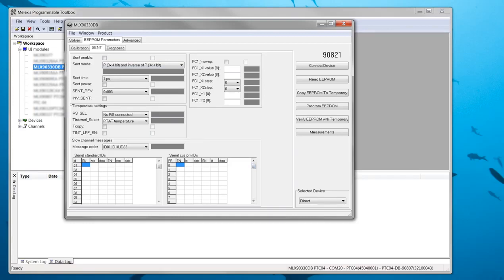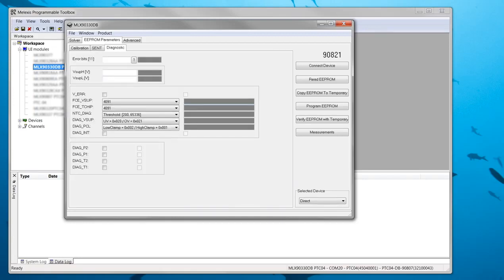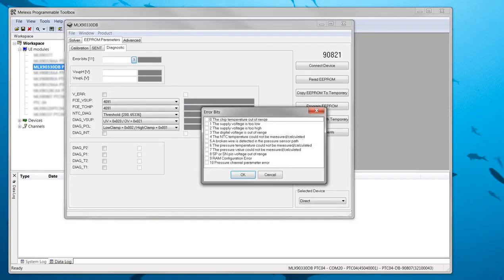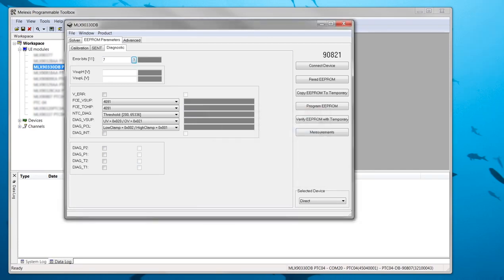The last group of E2PROM parameters relate to diagnostics. The most important parameter is the error bits. This selects which diagnostics will be flagged at the output. Pressing the question mark creates a window where you can individually add or remove flags. The thresholds for the over and under voltage flags can be set too. All other parameters in this tab are only used with the SENT output. They provide more options on how to report diagnostic information.